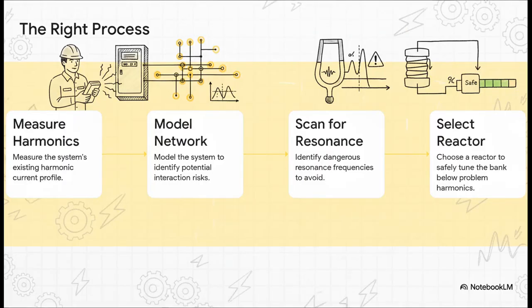And this isn't guesswork at all - it's a very methodical engineering process. You go on site, measure the specific harmonic fingerprint of a facility, model how the whole system is going to behave, and then carefully select the right reactor to tune the capacitor bank to a safe frequency, far away from any potential resonance points.